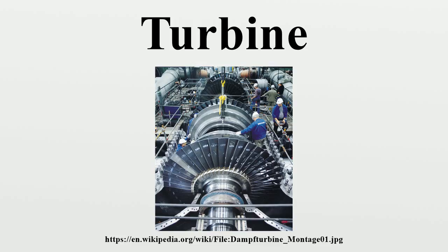Pressure compound multi-stage impulse, or Rateau, after its French inventor, Auguste Rateau. The Rateau employs simple impulse rotors separated by a nozzle diaphragm. The diaphragm is essentially a partition wall in the turbine with a series of tunnels cut into it, funnel-shaped with the broad end facing the previous stage and the narrow the next. They are also angled to direct the steam jets onto the impulse rotor.